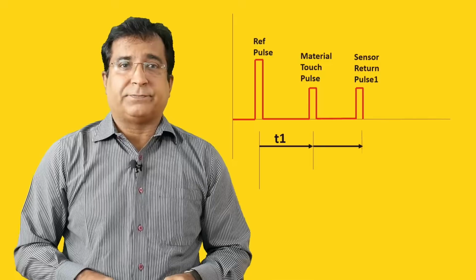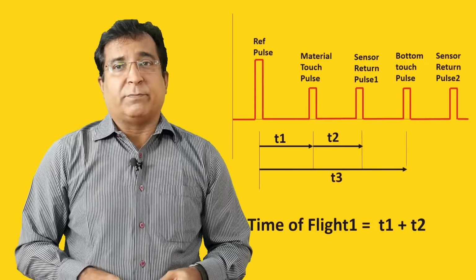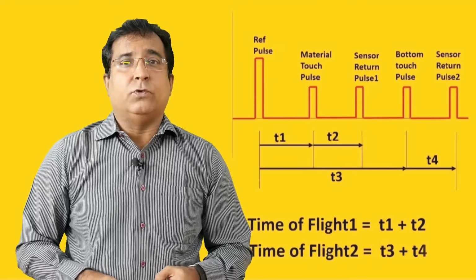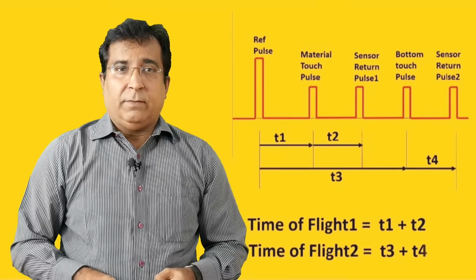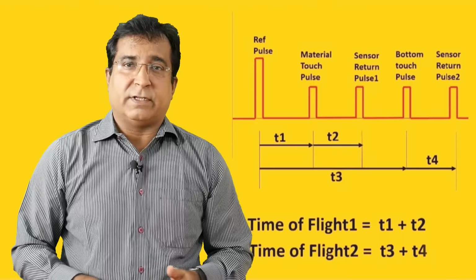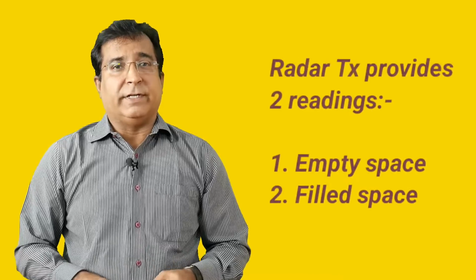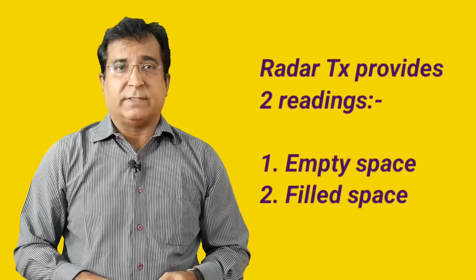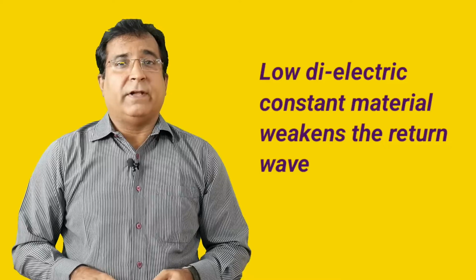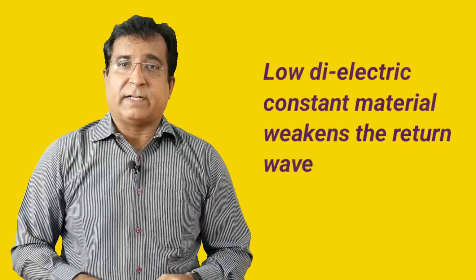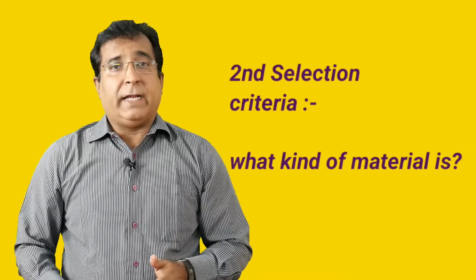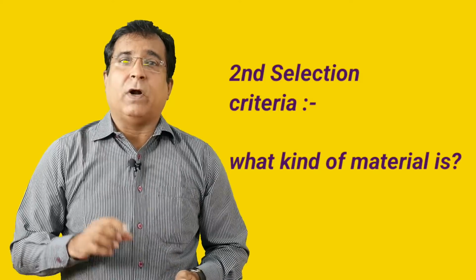This way you get two readings, one for empty space and the other for filled space. A radar transmitter with a digital network protocol like HART or fieldbus can communicate these two readings simultaneously to the control room. But a conventional 4 to 20 milliampere transmitter is not able to convey these two readings. It can provide only one reading, either filled or empty space. A radar sensor can pose a measurement problem if the dielectric constant of the material being measured is very low, as most of the wave will pass through the material and less of the wave will be reflected back to the sensor. So my second most important selection criterion will be the target material property, that is, density or dielectric constant.